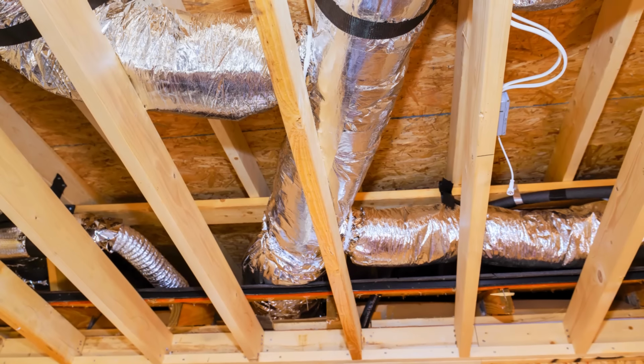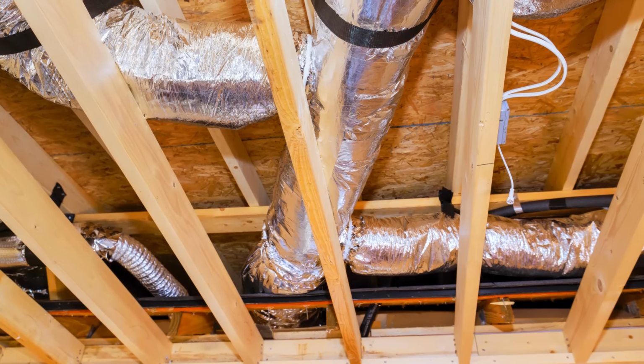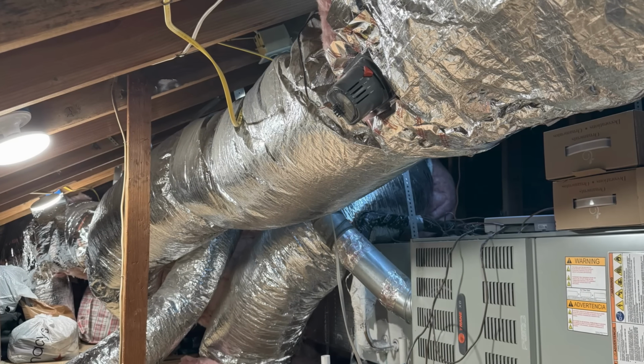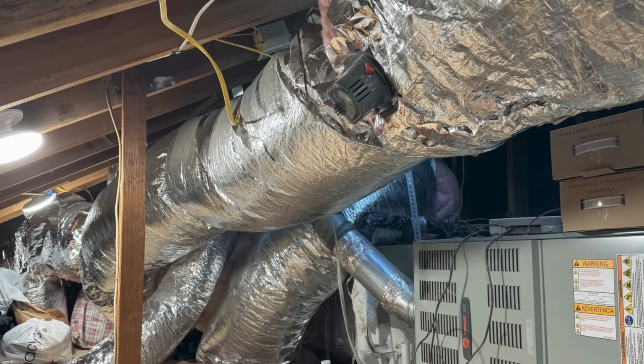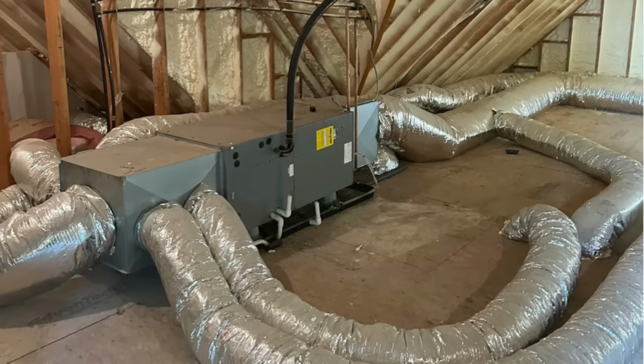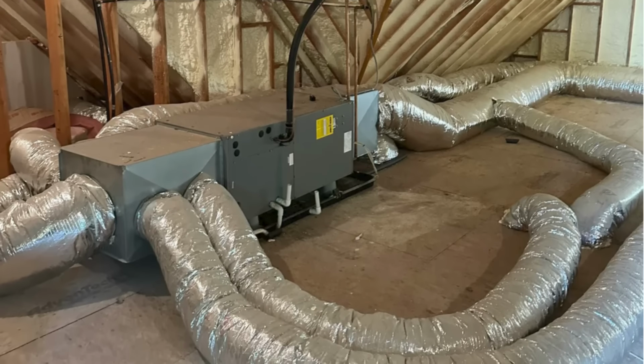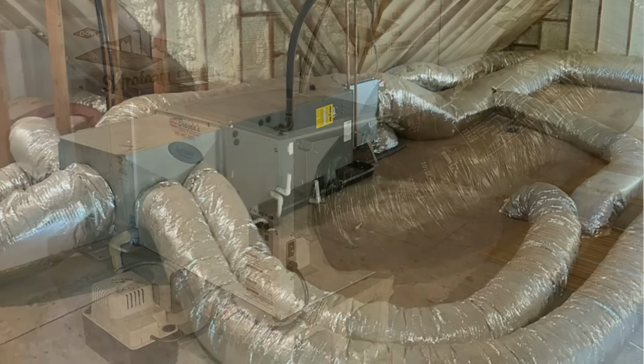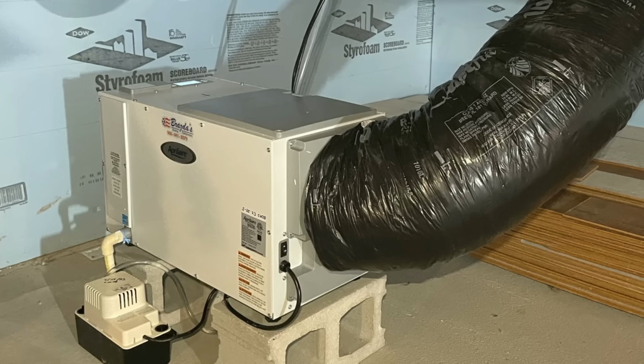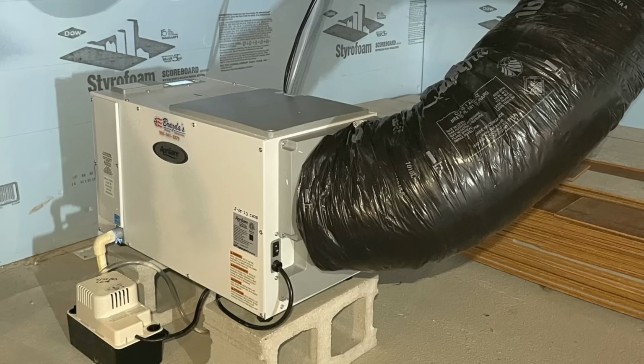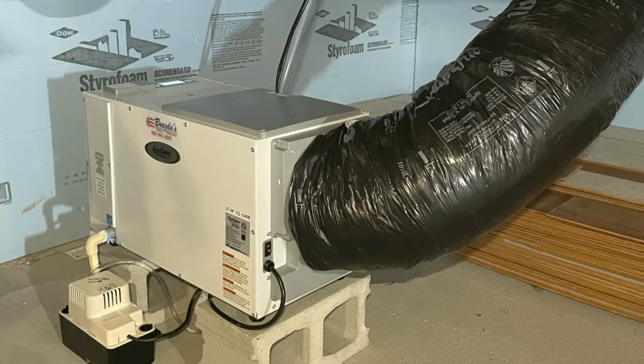Then we want to make sure that we're containing our ductwork within conditioned space. Don't let all that hot, humid air inside your interstitial spaces. The ductwork and air handler needs to be contained within the conditioned space to keep condensation from forming. And then we absolutely need supplemental dehumidification. This is your mechanical means of reliable and predictable moisture removal.